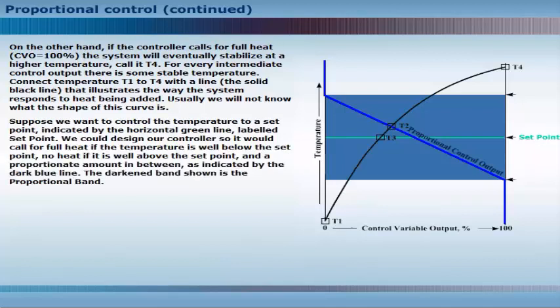Suppose we want to control the temperature to a set point, indicated by the horizontal green line, labeled set point. We could design our controller so it would call for full heat if the temperature is well below the set point, no heat if it is well above the set point, and a proportionate amount in between, as indicated by the dark blue line. The darkened band shown is the proportional band.